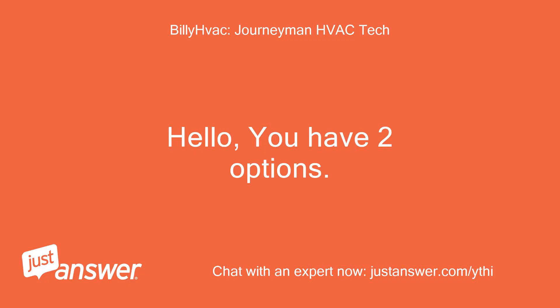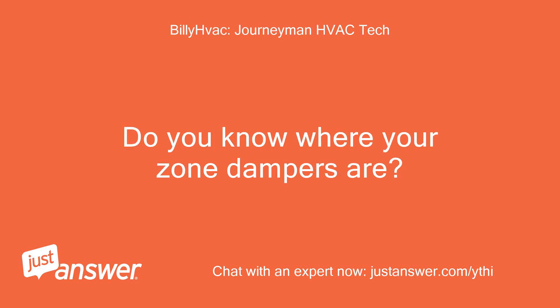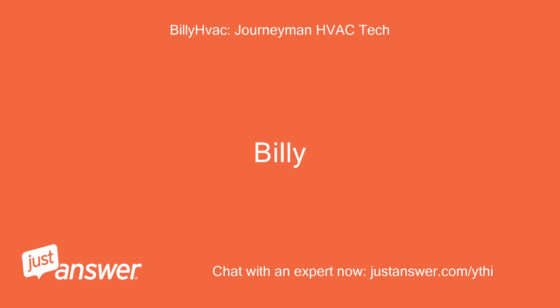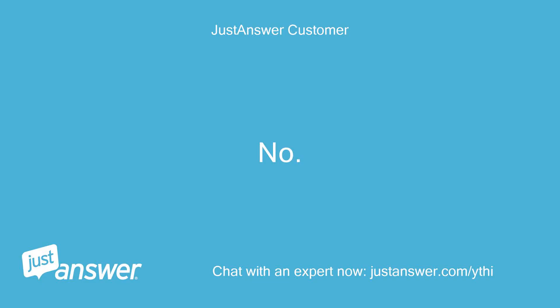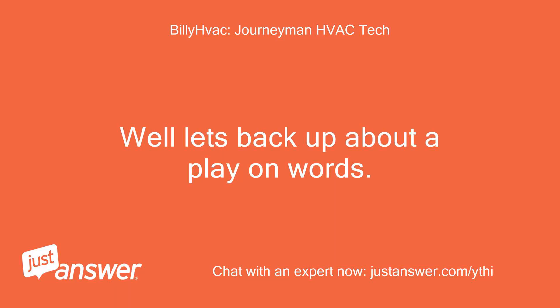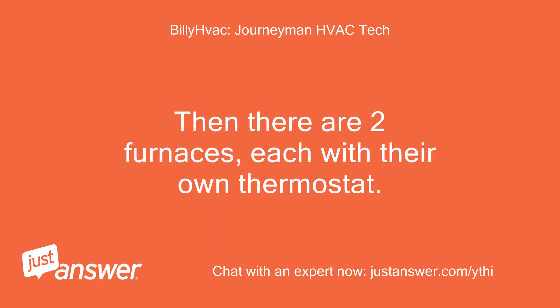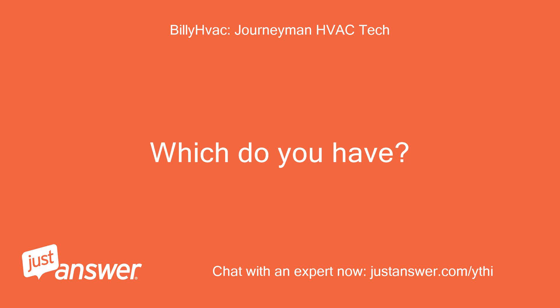Hello, you have two options: either the zone controller is defective, or the dampers are stuck open to the upstairs. Do you know where your zone dampers are? No. In the attic with the furnace? Well, let's back up — a play on words. I look at a zone system as one furnace serving more than one area with more than one thermostat. Then there are two furnaces, each with their own thermostat. Which do you have?